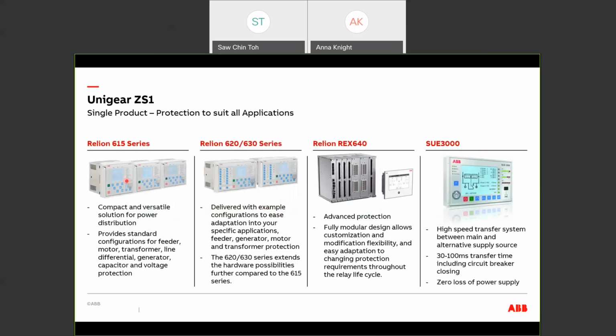The control and protection of the panel will be done through the protection relays. Depending on the protection required, we have the Relion 615 series, 620 or 630 series, and 640. The 615 and 620 or 630 relays have a set of pre-configured protection functions, suitable for example for feeders, REF, motor, REM, transformer, RET, line differential, RED, generators, REG, and capacitor, REV. So we have different protection relays already configured for different applications. The 615 series covers the basic and mid-range protections.